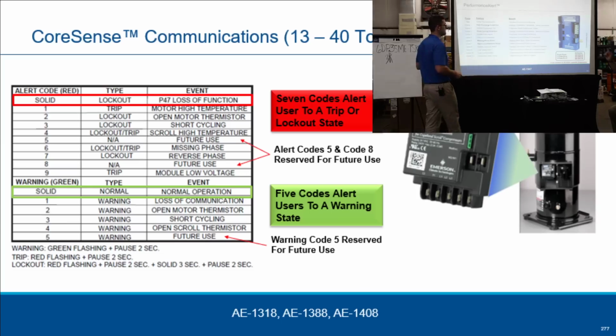Trevor, yeah? Real quick, you can use this. Trevor actually gave me this idea from technicians up there in Canada where we go up and work together a lot. You can also use that as a service tool. You don't have to permanently leave it on there. If you've got a problem child compressor, if you will, and you can't catch the problem while you're there, pop that on there, come back, download the information. It'll tell you what's wrong with it, what's going on.